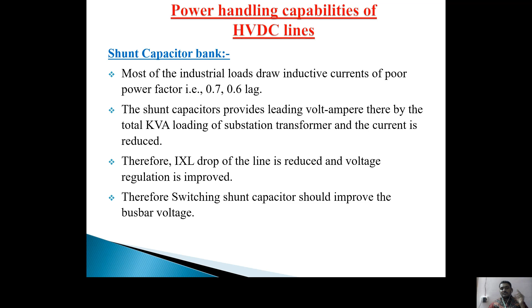The shunt capacitors provide leading volt ampere, thereby the total kVA loading of the substation transformer and the current is reduced. Therefore the IXL drop of the line is reduced and voltage regulation is improved. So switching a shunt capacitor should improve the busbar voltage.